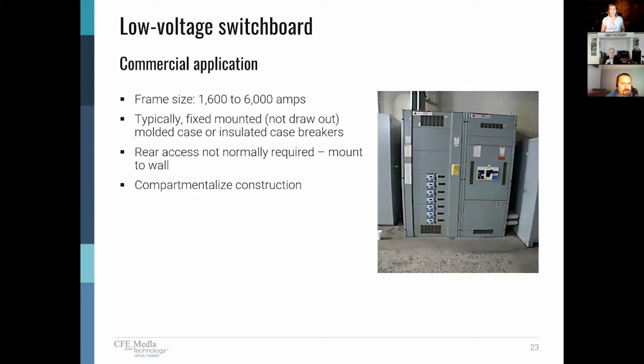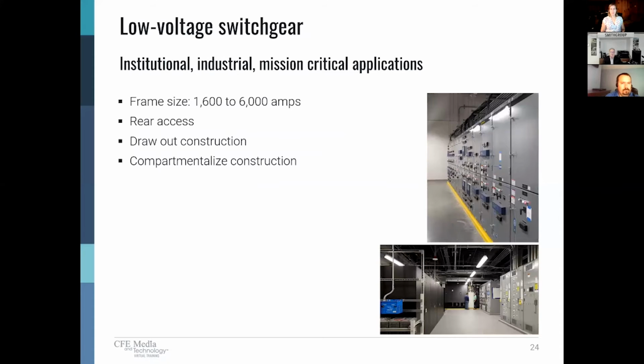So again, these are going to be much larger, almost universally floor mounted. They don't typically have draw-out breakers. That's an option in some models. They're normally fixed, so you're not going to have to deal with that clearance of drawing out a breaker. On most of these types of gear, rear access is not required. So you can mount these up against a wall, and the clearances that you need to work with are only in the front, possibly the side, but usually in the front. And they usually have compartmentalized construction. Next.